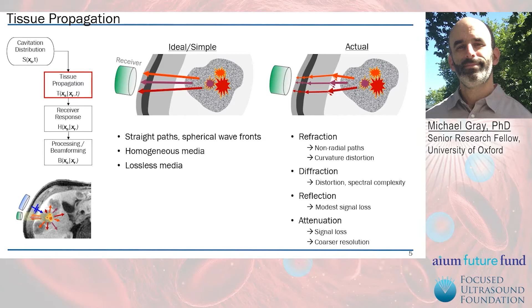Receiver response can be broken into two basic pieces. The first of these is electroacoustic response, which is set by construction of the transduction mechanism. Here I've got an example of measurements made on an L7-4 handheld array, where the bars indicate plus or minus 1 standard deviation across the 128 array elements. And I suppose some lessons learned from making measurements like this is that even though this is a well-made commercially available array, we can expect a pretty good degree of variability from element to element, and we shouldn't expect that the response will be uniform in the advertised response band.